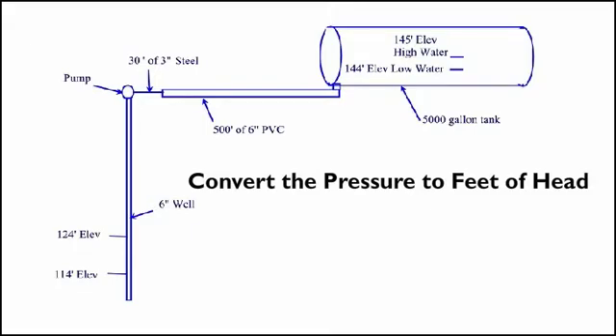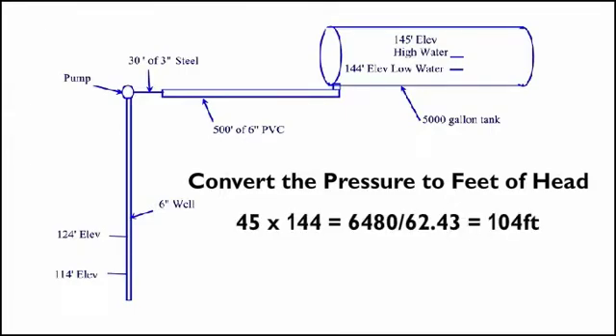You then need to convert the pressure from psi to feet of head. 45 psi is converted to feet of head first by multiplying 45 by 144 and then dividing by 62.43, which is the weight of a cubic foot of water. This comes to 104 feet, so the total is 104 plus 20 or 124 feet for the pump static head at rest.